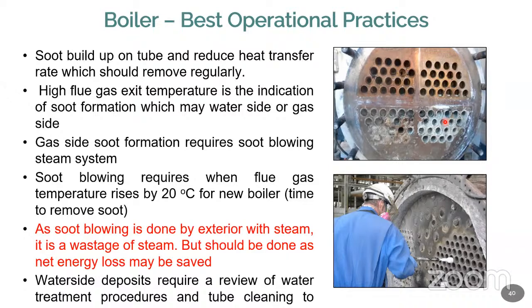And gas side soot formation requires a soot blowing system. That means you have to blow air, and the soot should be taken out. Soot blowing is required when the flue gas temperature rises by 20 degrees for a new boiler, and to remove it, soot blowing is done from the exterior with steam. Sometimes steam is also a wastage, but it should be done so that energy loss may be saved. Very important, you can use good quality water, and if it is a water tube boiler, the water quality should be very properly maintained. Most of the time, they regularly check the water quality as per IS 10500. They check the quality of the water by checking the TDS level, pH level, hardness, and other basic parameters like odor, smell, and all those things. And most of the time they use DM water or sometimes RO water also. Because of that, the scaling formation inside the tube will be lesser.